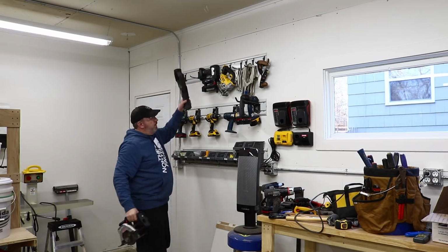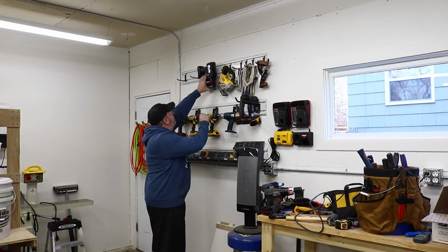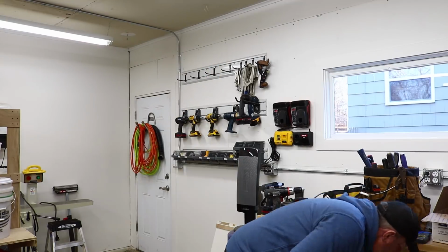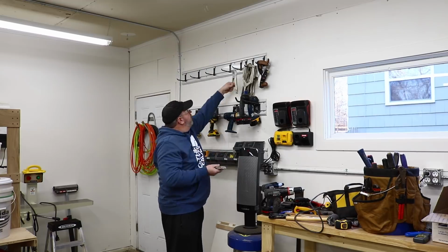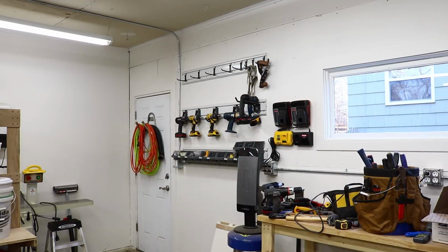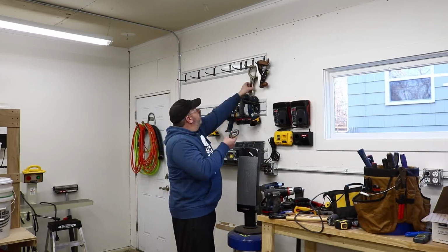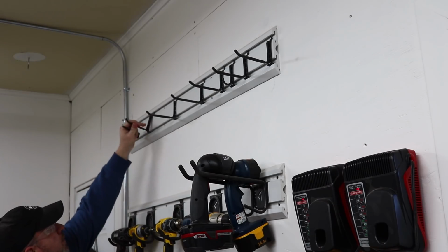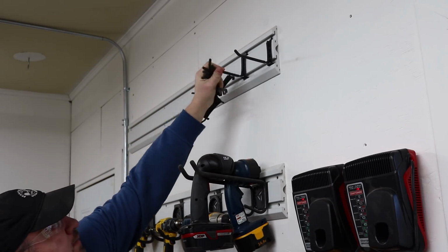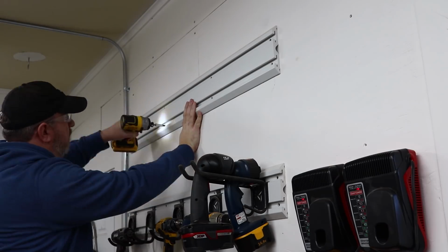The first step in installation is to mount the indoor unit. I debated on a few different locations in my shop and settled on placing it high on the wall between the door and the window. I picked this location because it is good for airflow and it is also the most convenient for the line set and electrical runs.